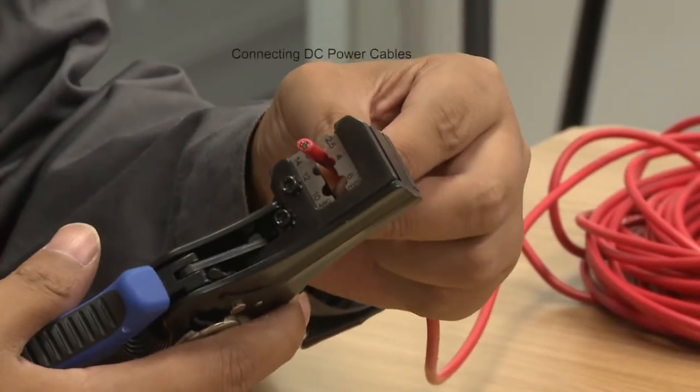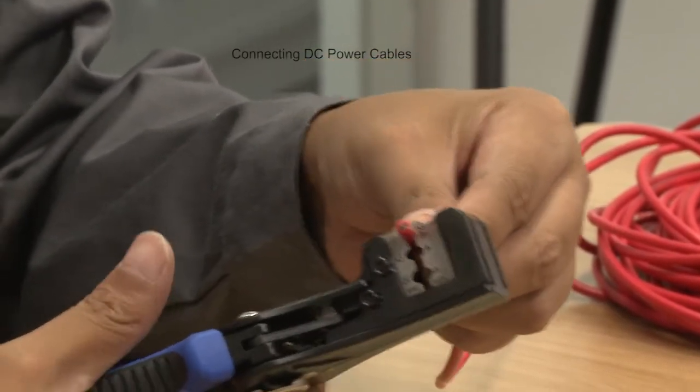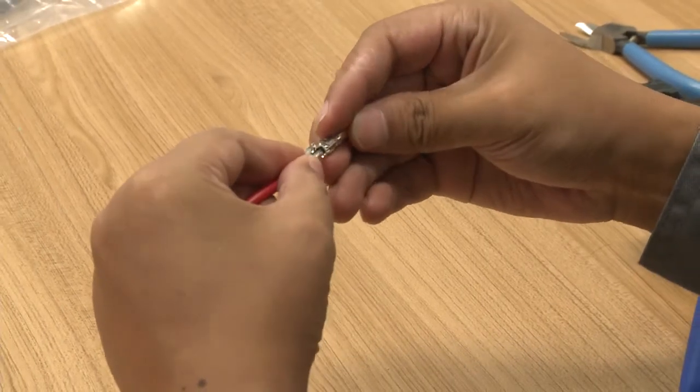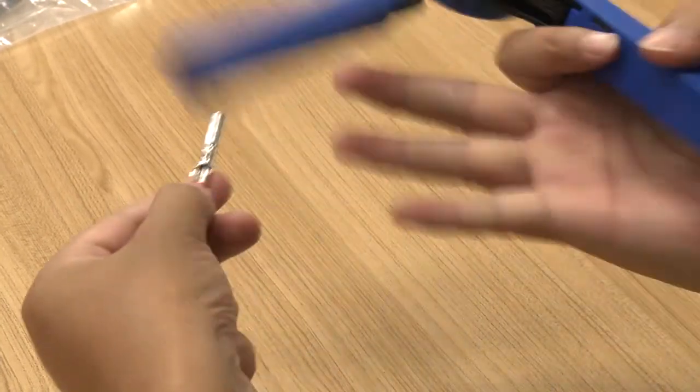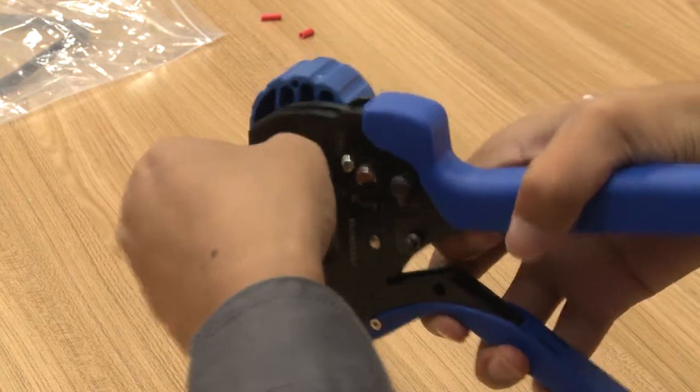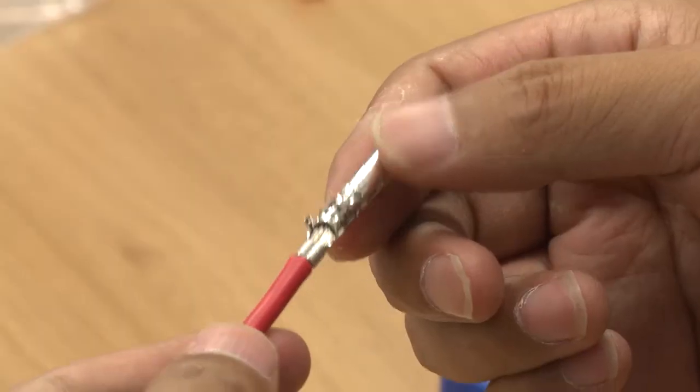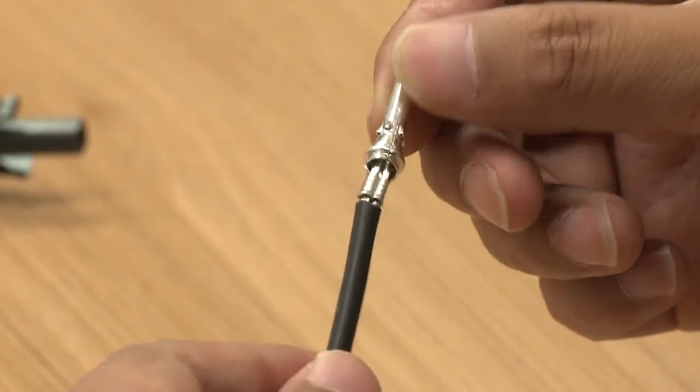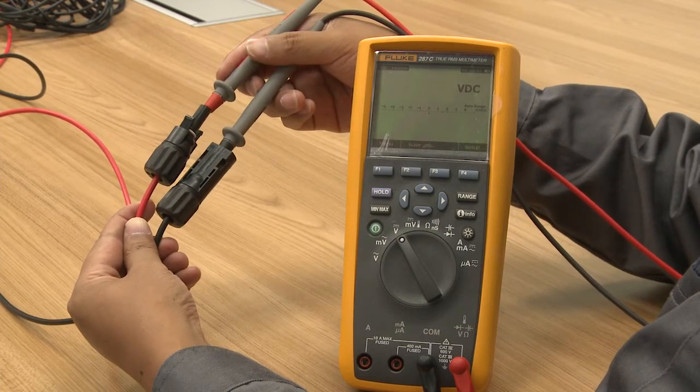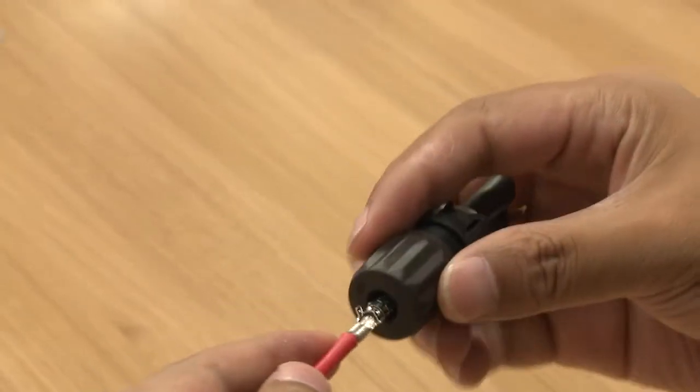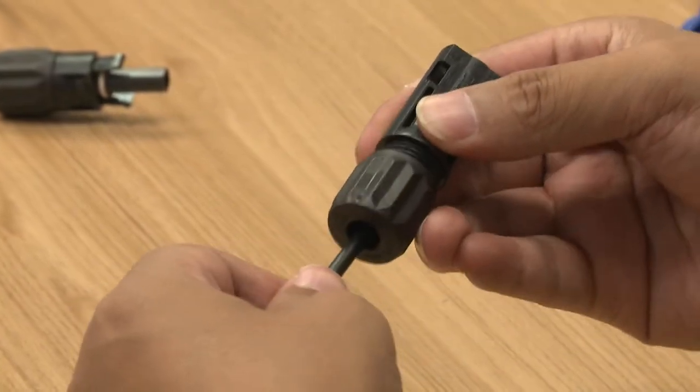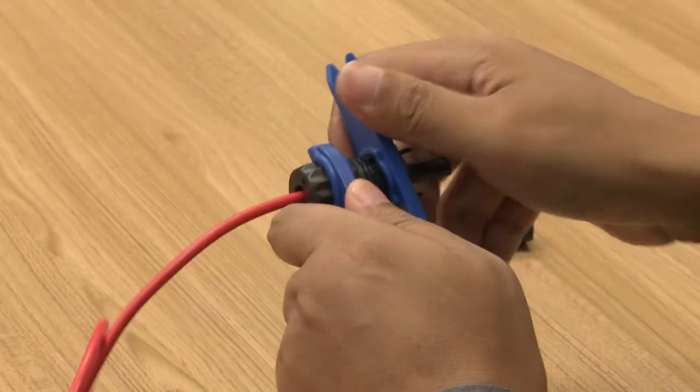Remove an appropriate length of the insulation layer from wires of the DC input power cables using a wire stripper. Insert the exposed area of the DC input cable wires into the metal terminals of the positive and negative connectors respectively and crimp them using the crimping pliers. Measure the voltage with a multimeter to ensure that the voltage of all DC terminals is within the normal range. Insert the crimped positive and negative power cables into the corresponding positive and negative connectors. Tighten the waterproof nuts using tightening tool.